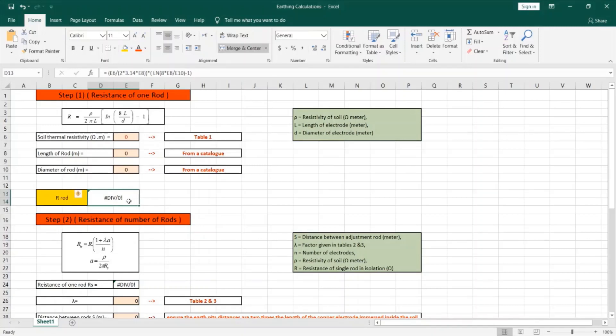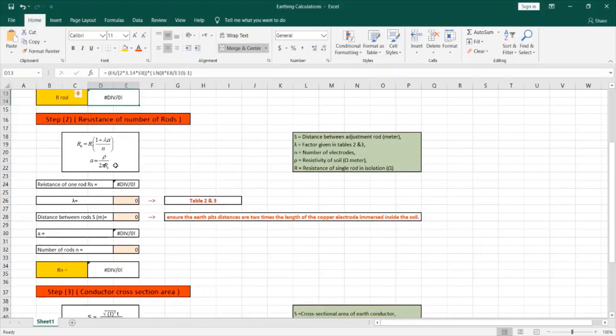The second step is for obtaining the resistance of more than one rod. The formula equals resistance of one rod multiplied by 1 plus the factor lambda multiplied by a, all divided by n, where n is the number of electrodes and a equals the resistivity of the soil divided by 2π multiplied by the resistance of one rod. This is the major step because we will be trying many options to reach a total resistance of less than 1 ohm.